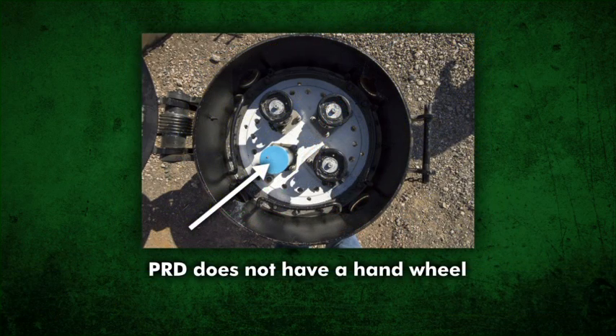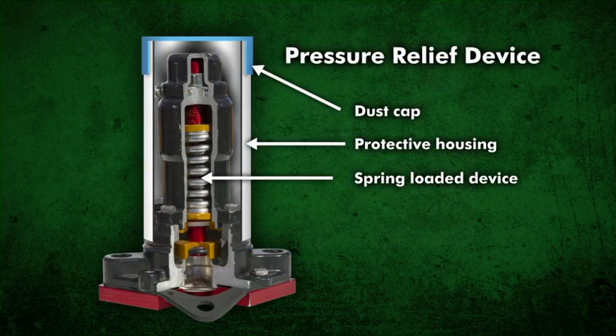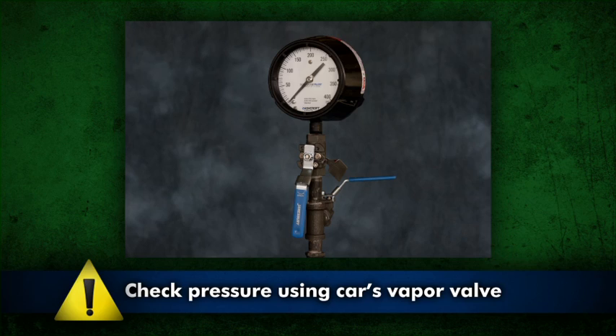From the top view, the pressure relief device looks different from the other angle valves because it does not have a hand wheel on it. This is a side view. The pressure relief device is spring loaded to only open in over-pressure situations. In over-pressure situations, it is functioning as designed and the C-kit should not be applied. Check the pressure using the car vapor valve if possible.